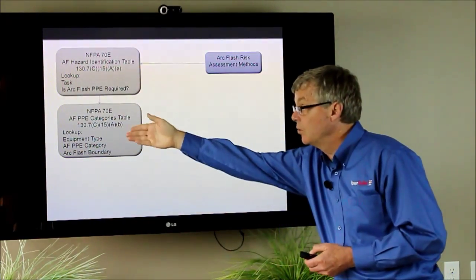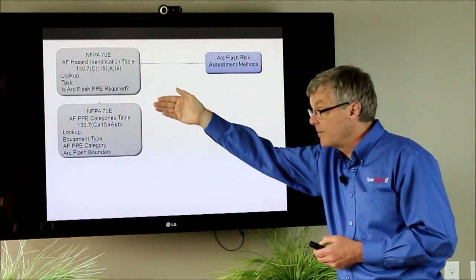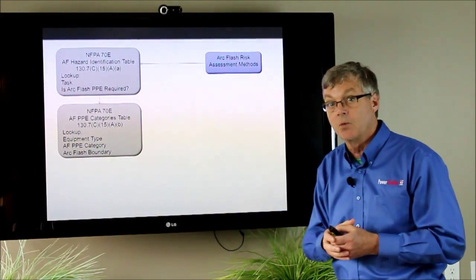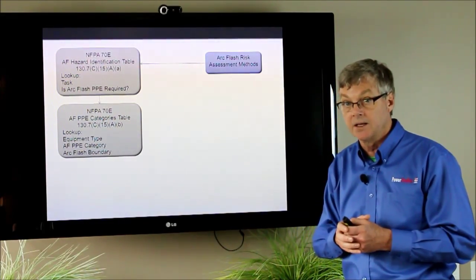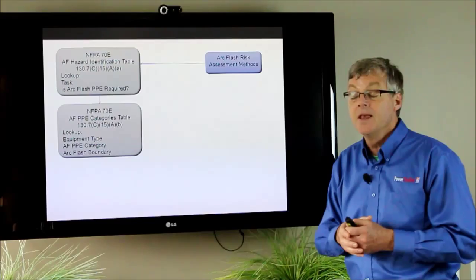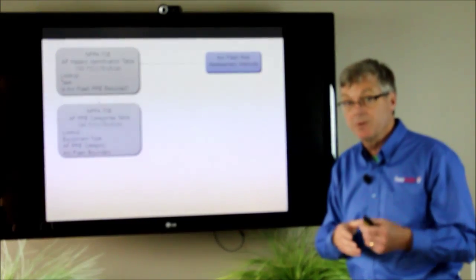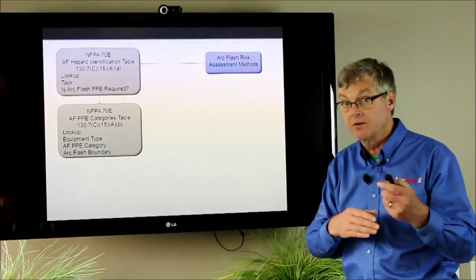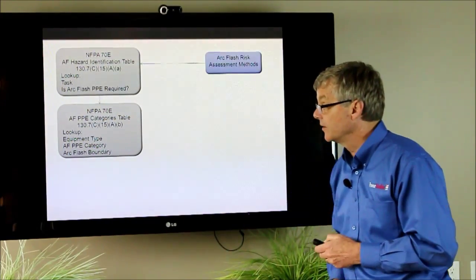And this only works though if you adhere to the table limits because at each piece of equipment they'll specify what the maximum short circuit rating is or available fault current and what the maximum tripping time has to be. If you exceed any one of those values, short circuit or tripping time, you can't use this method.